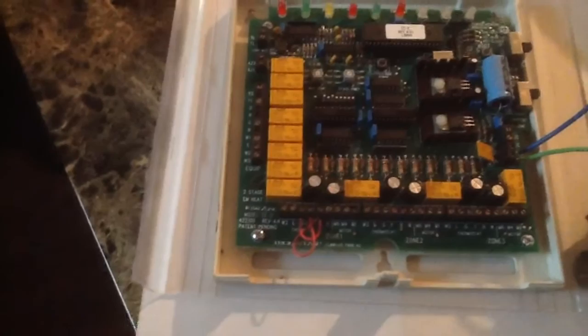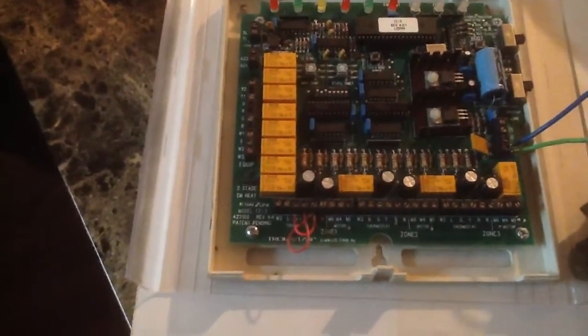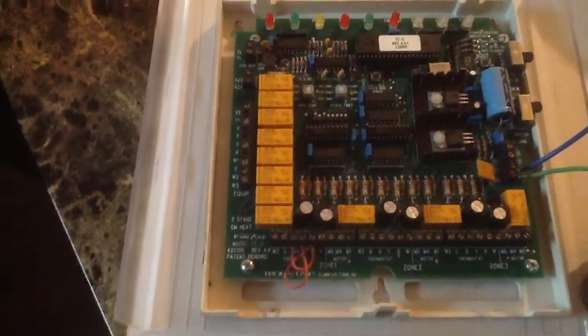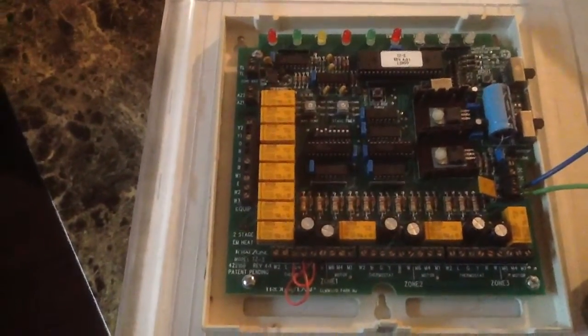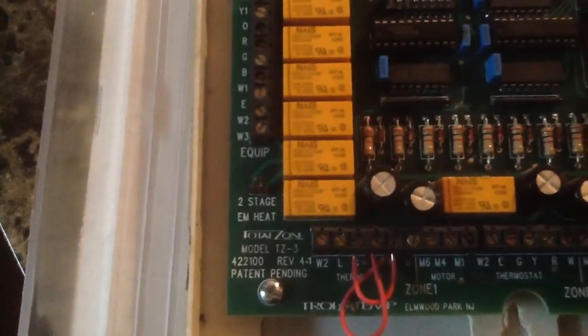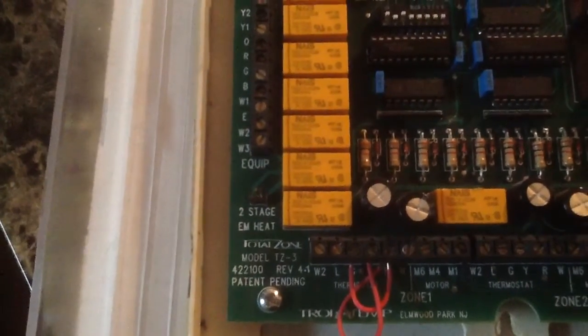work on them. Basically, what you have here is a board, and you'll notice on the left side here is equipment, and then you have all your terminals. Those terminals are going to your equipment, whether it's an air handler or a gas furnace or whatever. And you'll notice over here you'll see zone 1, and on the left side it'll say thermostat, on the right side it'll say motor.